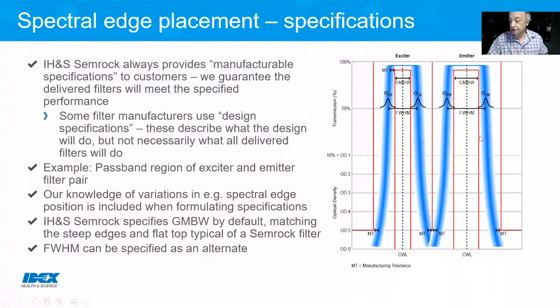So the illustration to the right here can be used to understand some of this. The orange lines indicate constraints on spectral performance of this exciter-emitter bandpass filter pair. The left one, for example, shows a red line which corresponds to the guaranteed minimum bandwidth of the filter, which is essentially the pass bandwidth in nanometers over which the transmission will be 90%. It is a little different, as you can see, from the full width half maximum. The other constraint lines include this OD definition here, and then the necessity of a separation in OD between these excitation and emission pairs so that there's a kind of what is called a crossover point, and of course others.